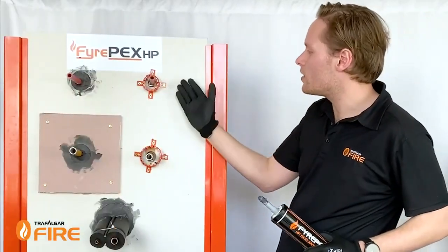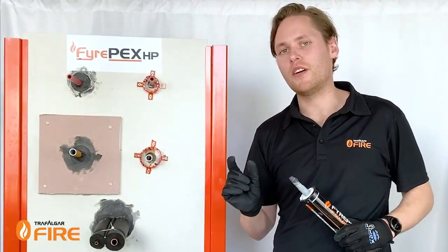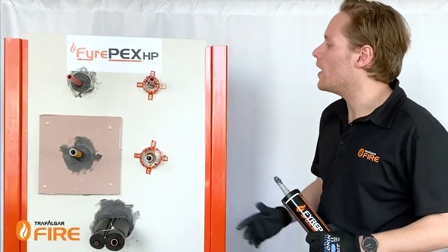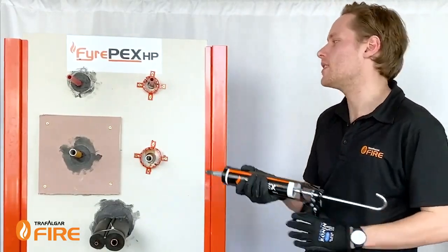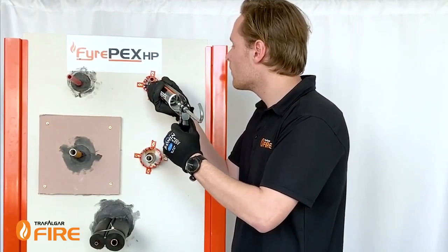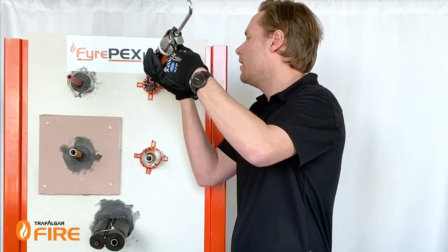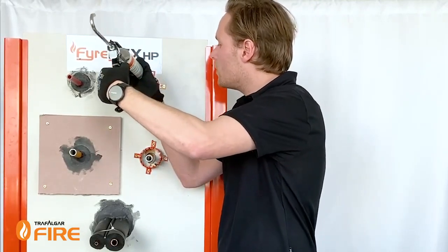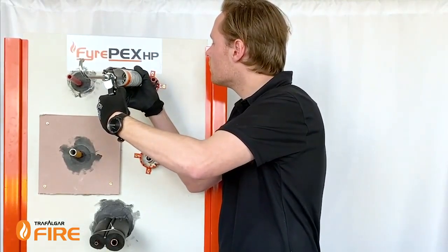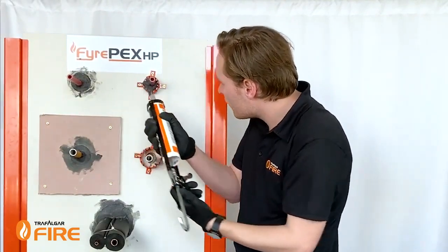I've already installed some here — we install these into plasterboard walls using 8-gauge by 25mm plasterboard screws. All we have to do now is fill in the annular gaps with our FyrePEX sealant. As you can see, it's much easier to fill the gaps here and we're not losing any sealant into the cavity of the wall. You just need to fill it up so it finishes flush with the front of the collar.